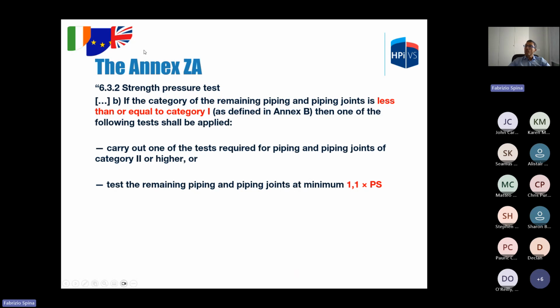This is the option for category 1 or lower. You can carry out the test required for piping of category 2, of course, so you can apply a stricter requirement, or test the piping at 1.1 PS. So when you have an assembly with piping of category 1, you can just perform a pneumatic test.